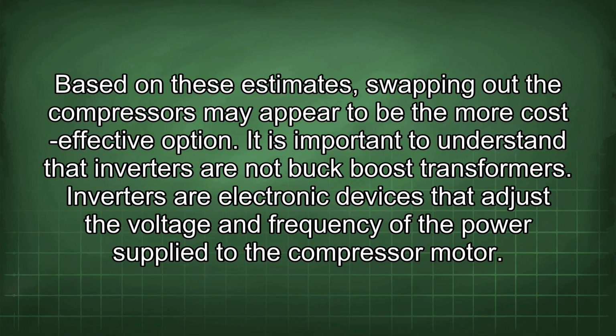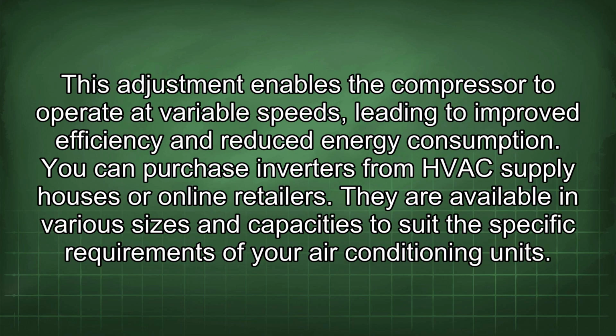It is important to understand that inverters are not buck-boost transformers. Inverters are electronic devices that adjust the voltage and frequency of the power supply to the compressor motor. This adjustment enables the compressor to operate at variable speeds, leading to improved efficiency and reduced energy consumption. You can purchase inverters from HVAC supply houses or online retailers. They are available in various sizes and capacities to suit the specific requirements of your air conditioning units.